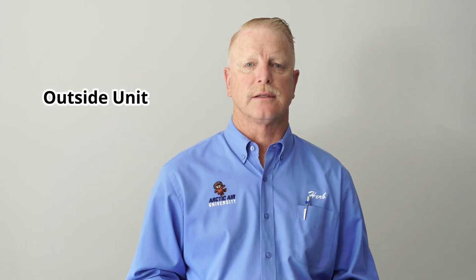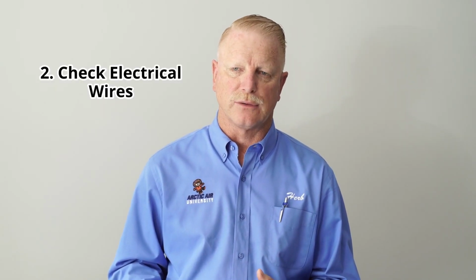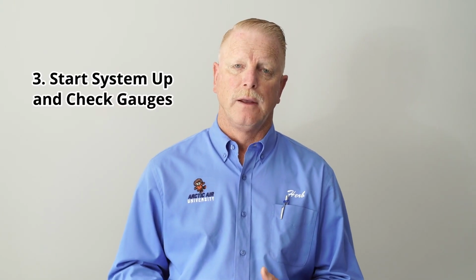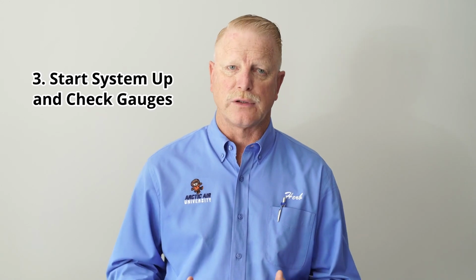Then we get outside, we turn the system on. Before we actually get it running, every AC unit has a capacitor in it. We are going to check your capacitor. This gives the unit a boost on running for both your compressor motor and your fan motor outside. Once that is checked, we're going to check all your electrical wires on that to make sure there is no burnt wires, loose connections. That could cause a burnt wire and a nuisance breakdown for us. Then we're going to start the system up, put our gauges on it, refrigerant gauges that is, and see what kind of pressures you're running at. Your refrigerant should be at proper levels. We have several ways of testing that, and we will do that. After that, we'll do an amp draw on your compressor motor and your outdoor fan motor to make sure they're not struggling and there's no issues with them.